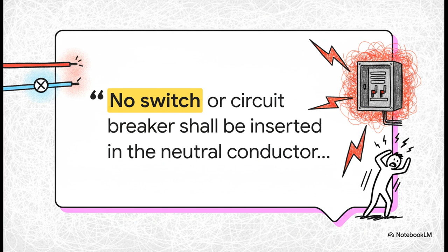And when things are wired incorrectly, the results are terrifying. No switch or circuit breaker shall be inserted in the neutral conductor. Why is this hard and fast regulatory rule so crucial? Well, because if a changeover switch open-circuits the protective earth neutral, the PEN conductor, the entire earthing system of the site, including the metal switchboard itself, can become fully energized. It literally turns the very safety mechanism of the house into a lethal hazard.